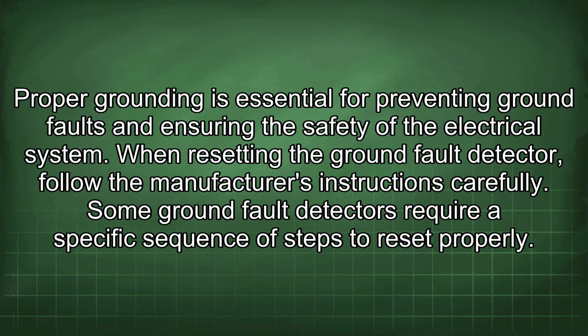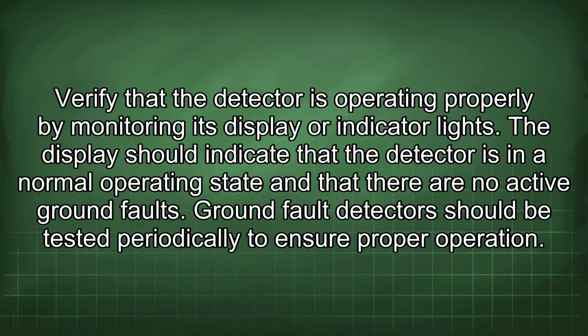When resetting the ground fault detector, follow the manufacturer's instructions carefully. Some ground fault detectors require a specific sequence of steps to reset properly. Verify that the detector is operating properly by monitoring its display or indicator lights. The display should indicate that the detector is in a normal operating state and that there are no active ground faults. Ground fault detectors should be tested periodically to ensure proper operation.